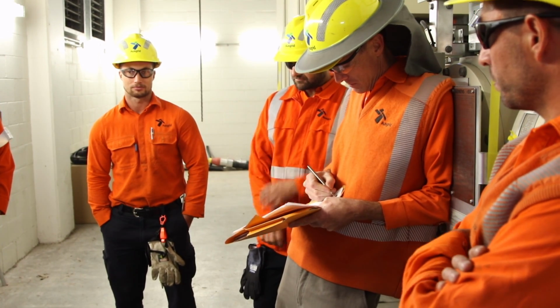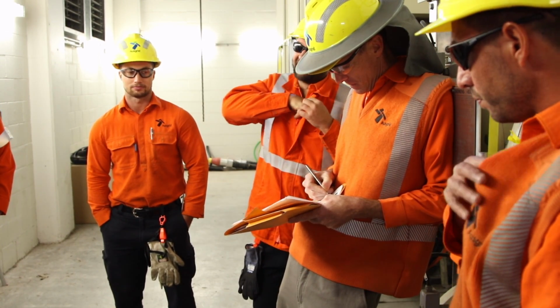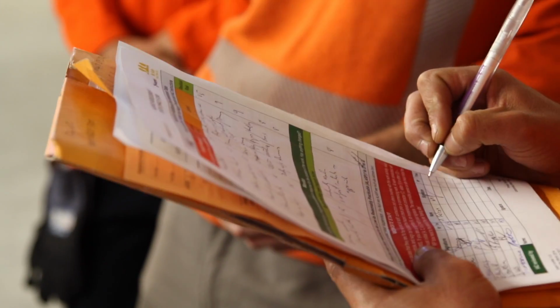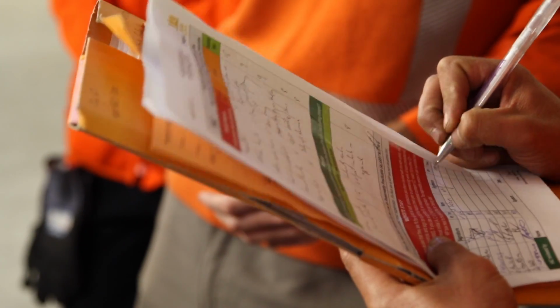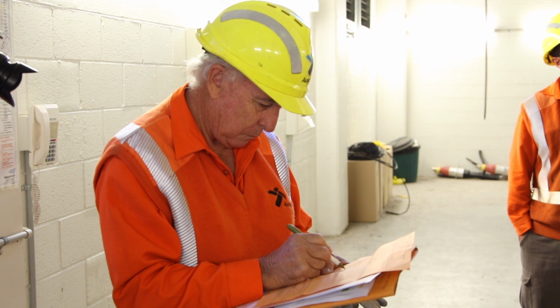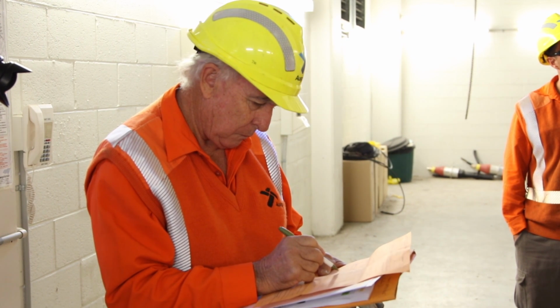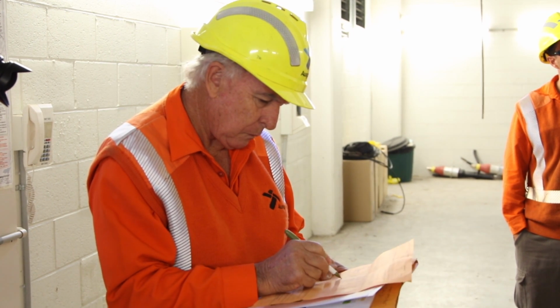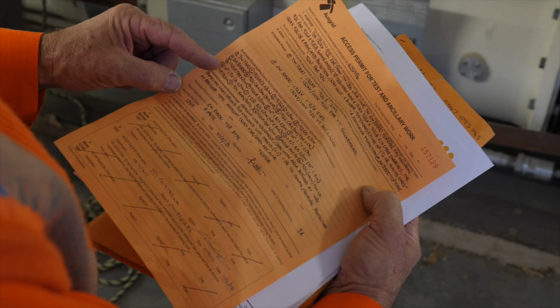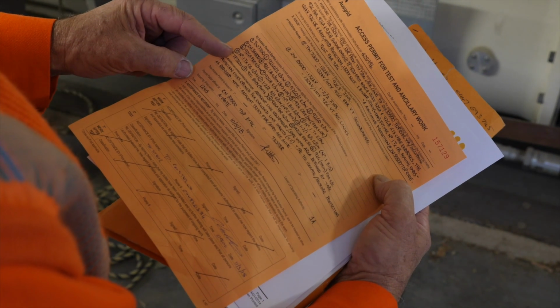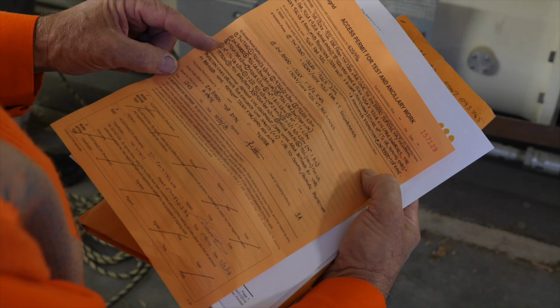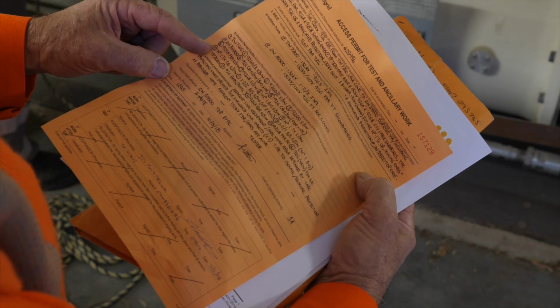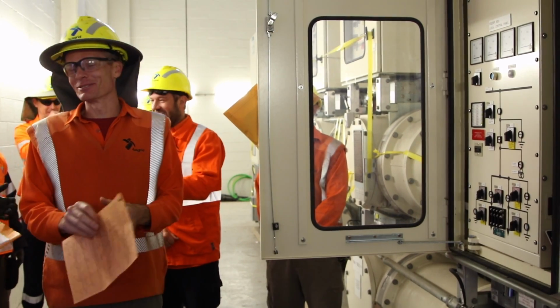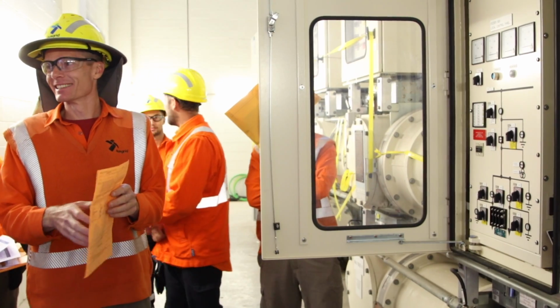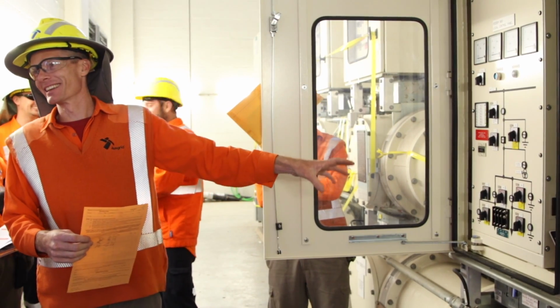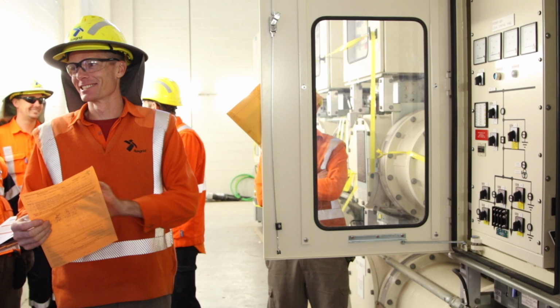The work group then signs the HAC document to show that they have understood the dangers and the required controls for us to safely complete our work. An access permit is required to gain access to the part of the network for the required work. A test and ancillary permit is required on the test object, which allows the application of high voltage. On the access permit, there are isolations and earthing to provide safe access to the network. These are checked against the system diagram to ensure they are correct for their purpose.